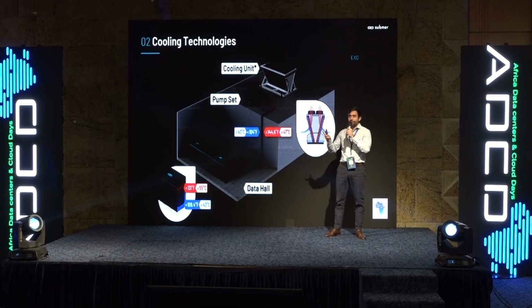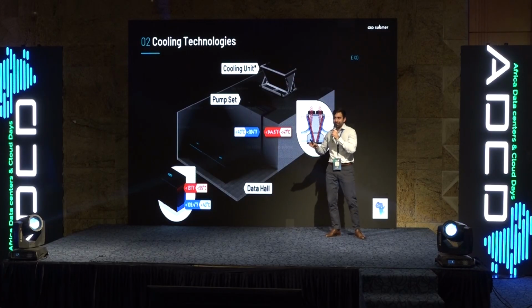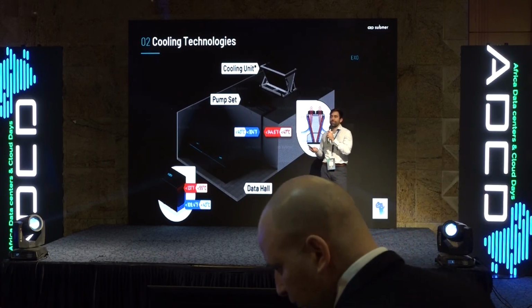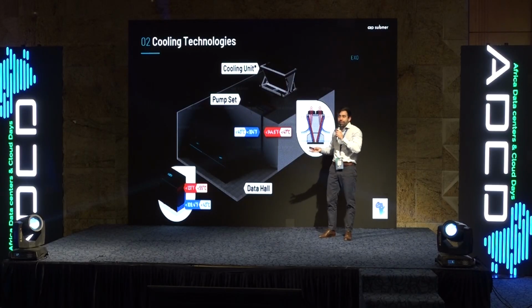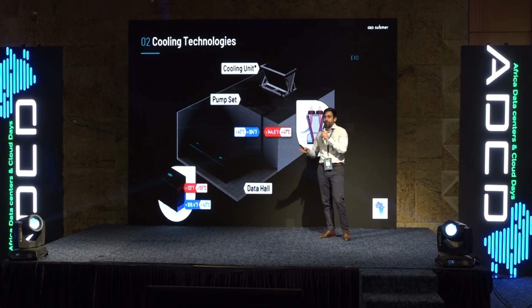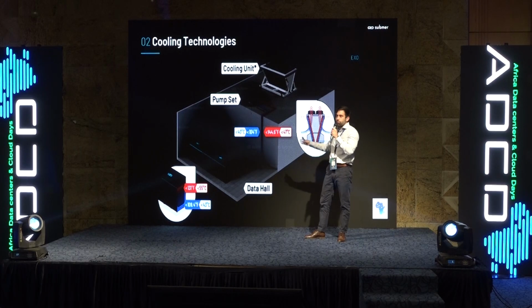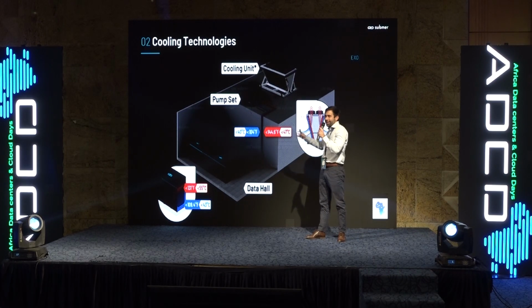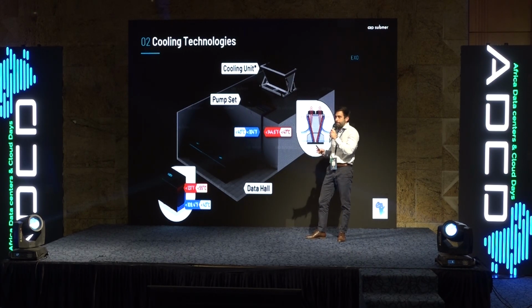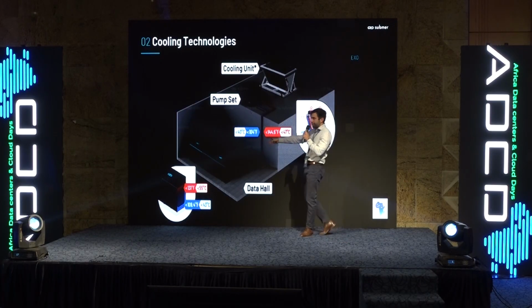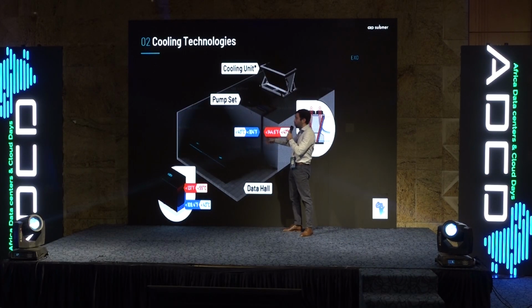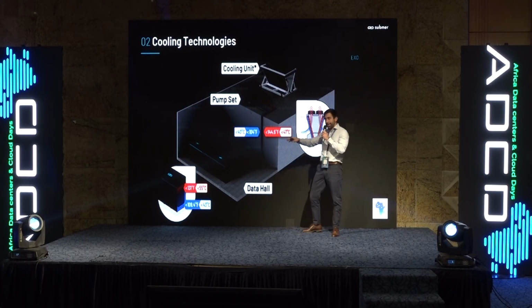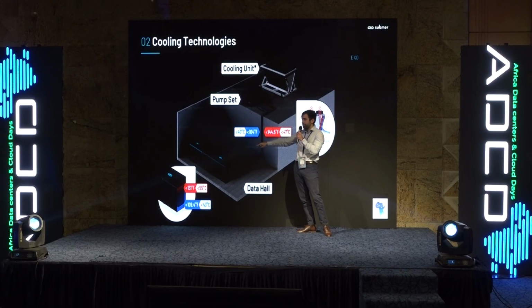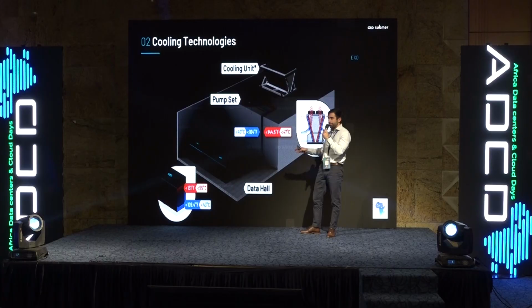For your question about at what kilowatt level I need to switch to immersion cooling — my answer is always that it depends on the type of business you have. In the past, we used to think about immersion cooling just for high power density, AI, so more than 100 kilowatts. But if I have 100 kilowatts, I'm going to need colder water than if I have 50 kilowatts. So the main driver for this client I have in Egypt, who I'm visiting tomorrow, isn't that they have a really high power density solution — it's that they want to improve the PUE.